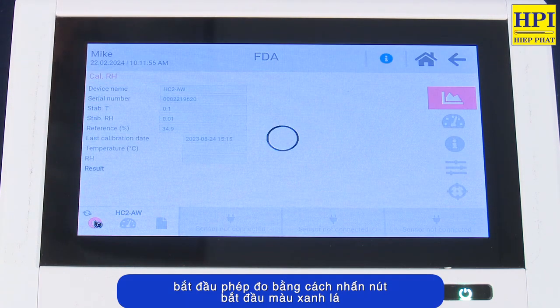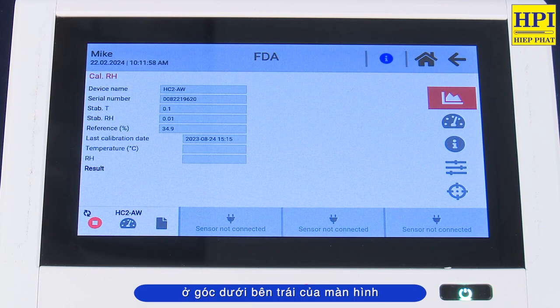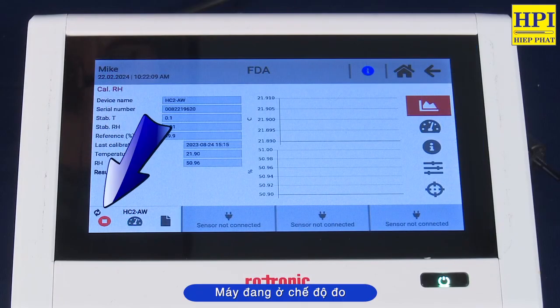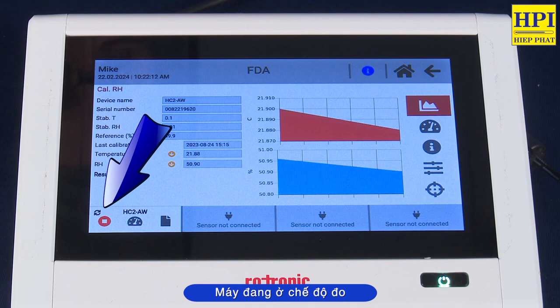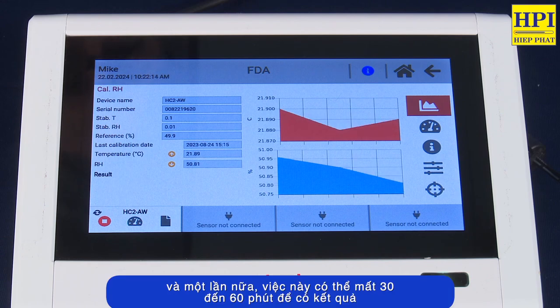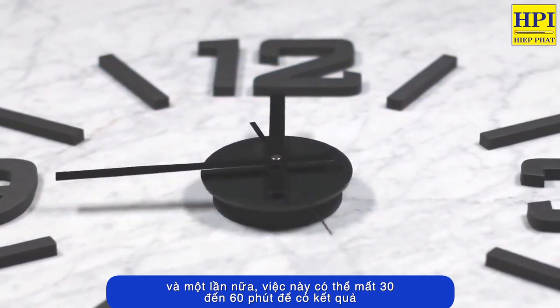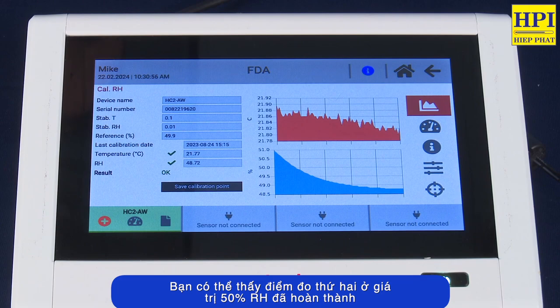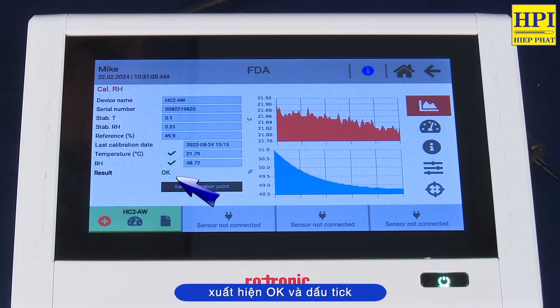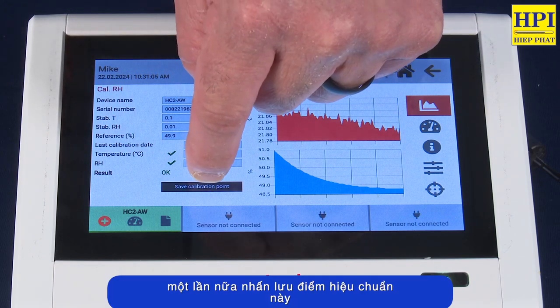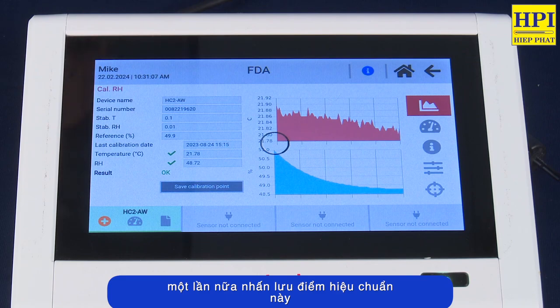We're going to start a new measurement by pressing the green start button in the lower left-hand corner of the display. As before, the two spinning arrows indicate that we are now in measurement mode. And again, this could take 30 to 60 minutes for the result to be completed. So as you can see, our second measurement point at 50% RH has completed, as evident by the OK icon next to the result. We want to once again go ahead and save that calibration point.